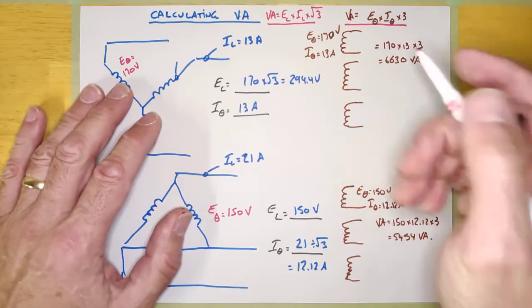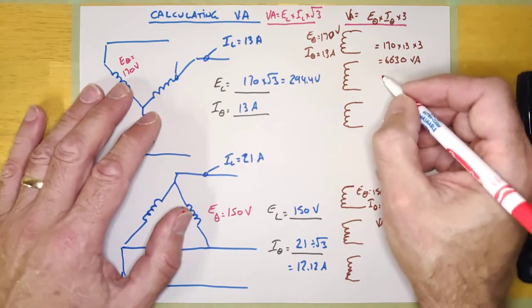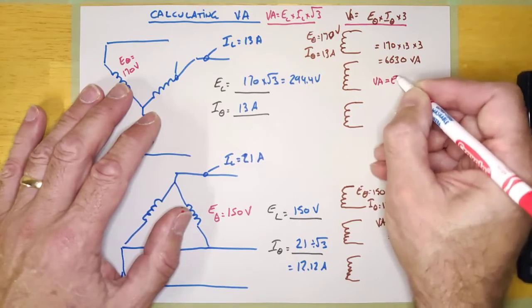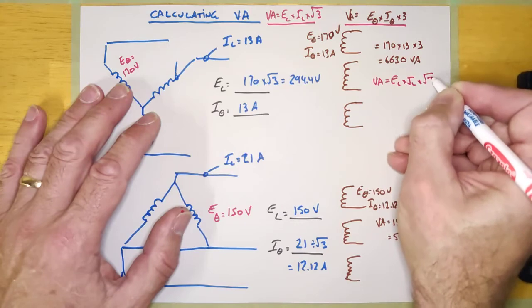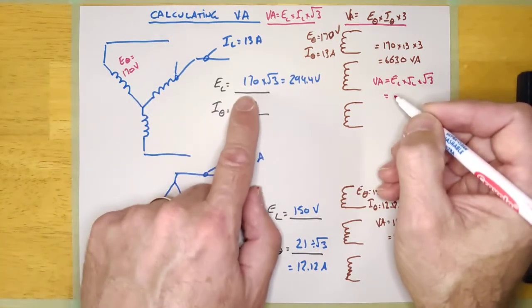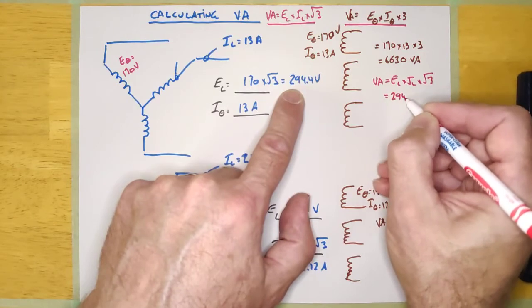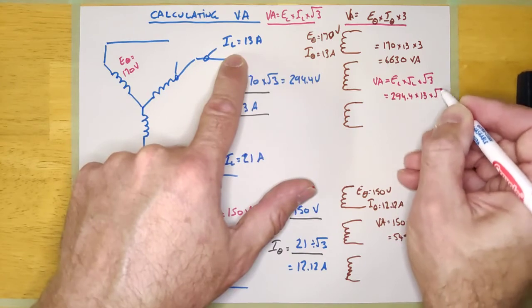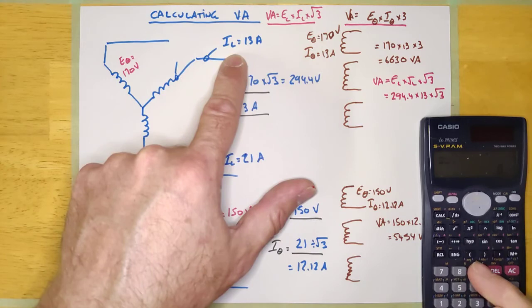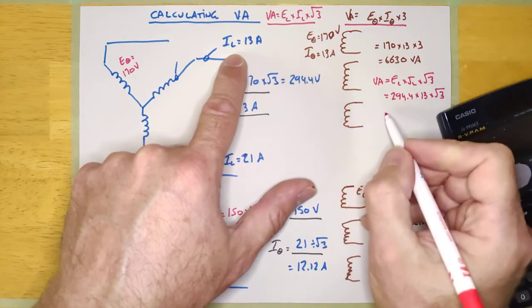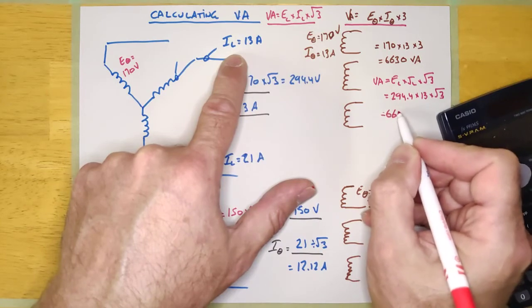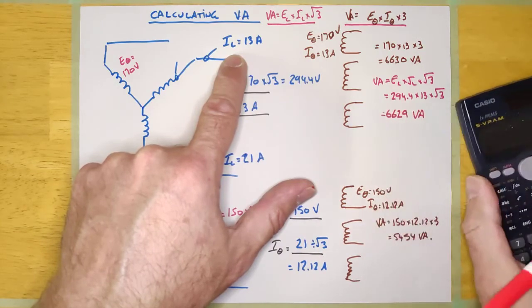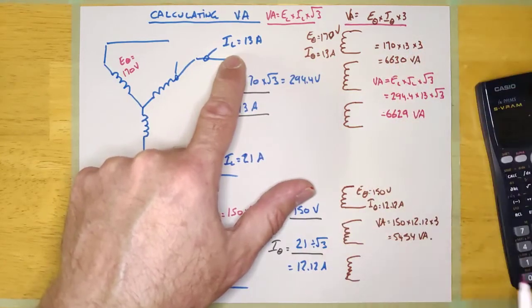Let's try that same formula using line values. VA = E_line × I_line × root 3. On this Y transformer, that's 294.4 times 13 times root 3, which gives us 6,629 volt amps — same as before.